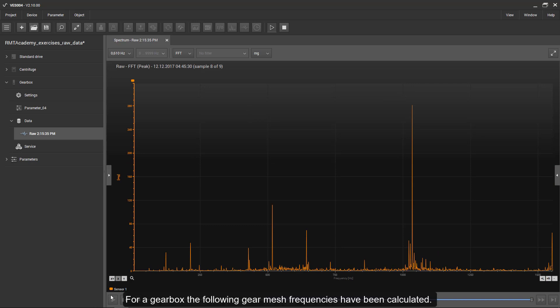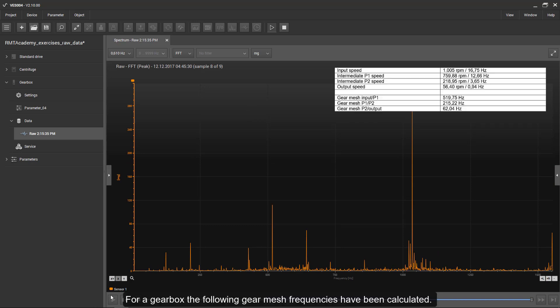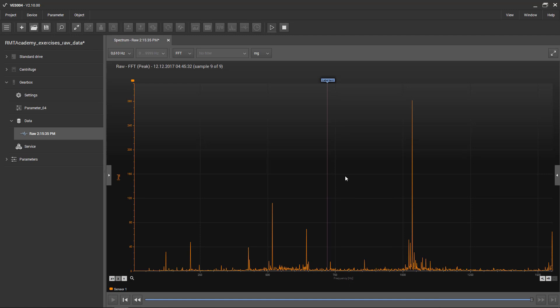For a gearbox, the following gear mesh frequencies have been calculated. These fault frequencies can be marked in the spectrum by adding labels.